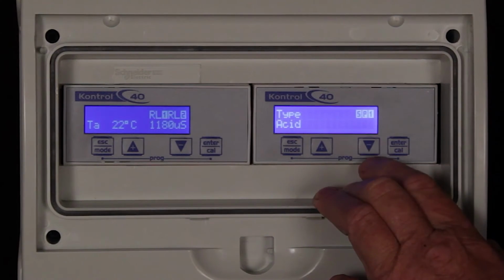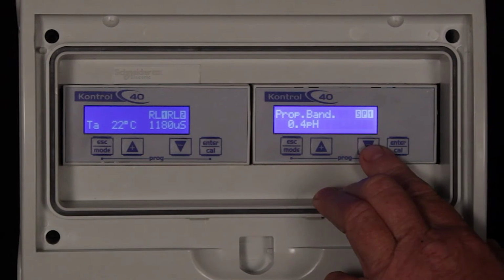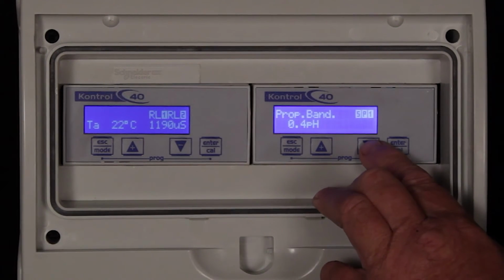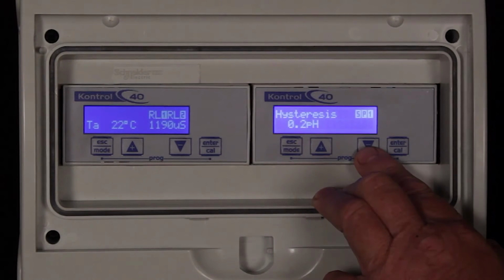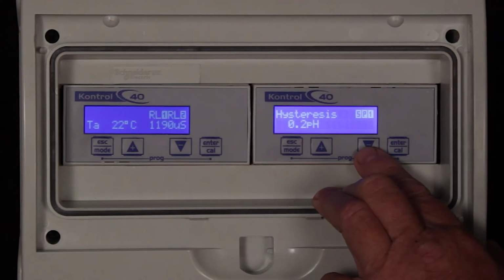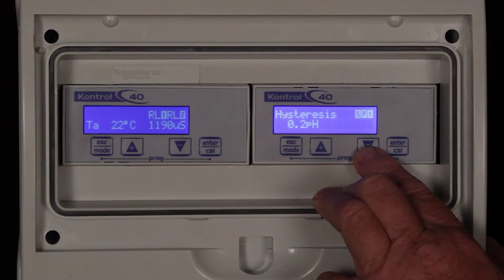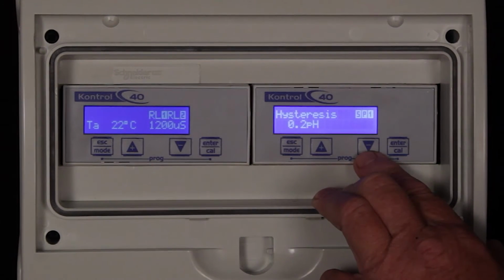This value is now set to acid and the controller knows that I want to lower my pH. Proportional bandwidth is 0.4. This is the default lowest setting. The hysteresis is the deviation value where the pump will turn on. If the set point is 6, the pump will switch on at 6.2 if the hysteresis is set to 0.2.